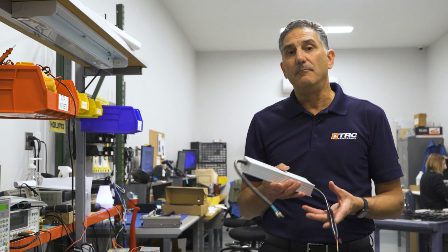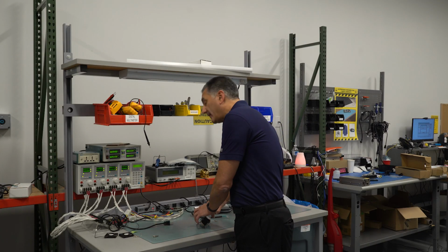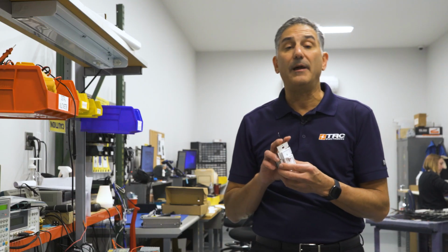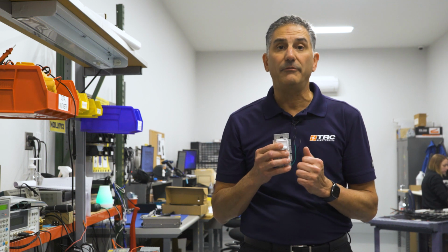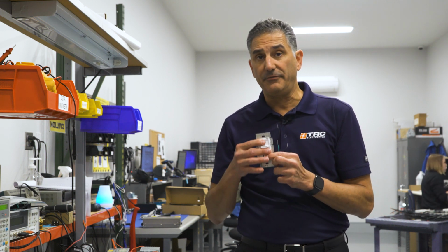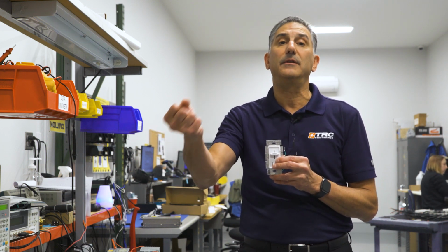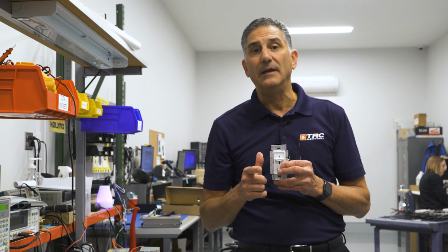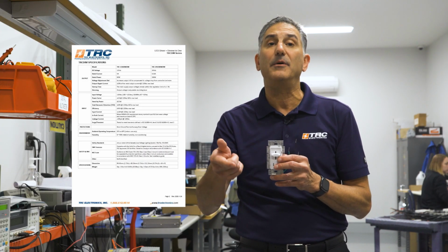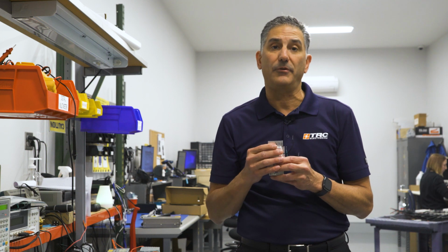Now, when connecting multiple fixtures to one dimming circuit, it's important that you actually check the dimmer itself and make sure that it can handle the multiple different streams of current that it's going to draw from the LED drivers and the LED fixtures. The more drivers you have connected to the dimmer, the more current is going to be drawn in. So it's important to note, and this is not very obvious, but in the dimming driver data sheet, there will usually be a designation for how much current is going to be made available from each driver, depending on what setting you have for the dimming function.